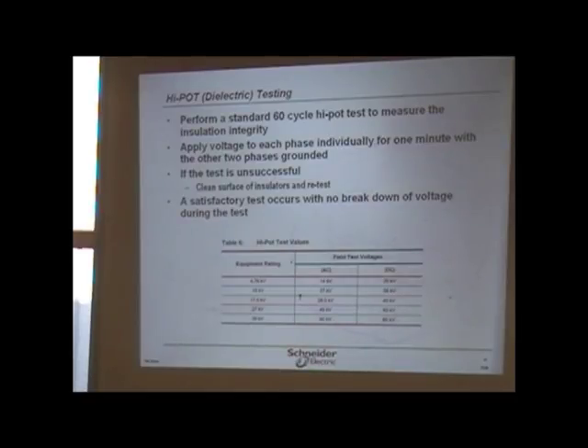the vacuum in those models are good. So it hasn't lost vacuum. This hasn't lost pressure, and that's the whole purpose of high pot. Where a megger is you're making sure that there's no grounds per se. Right. And that's the whole purpose of the megger. This has to do more with the integrity of the gas or vacuum and something like that, the other of the equipment.